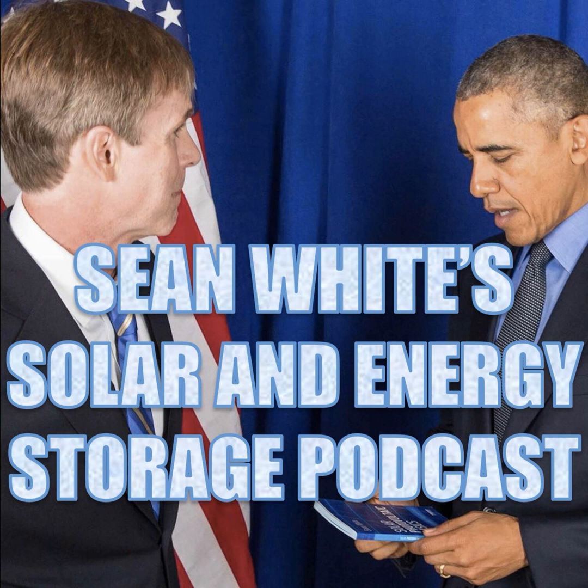But in the field and other places, when they mean bonding, they say grounding. So a lot of times when people mean bonding, they say grounding. In fact, the wire that does the bonding is called the equipment grounding conductor. Why isn't it called the equipment bonding conductor? But it's called the equipment grounding conductor, the EGC. The EGC, the equipment grounding conductor, that does bonding. And grounding could be done by the equipment grounding conductor. And so remember we talked about those Article 200 wires being white. Well, these grounding and bonding conductors are typically green or bare. One of the reasons why they can be bare is because you want them to bond to things. You want them to touch more things. The more things they touch, the better job they're doing.